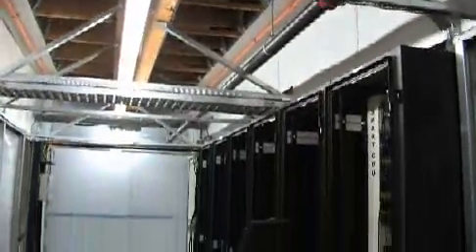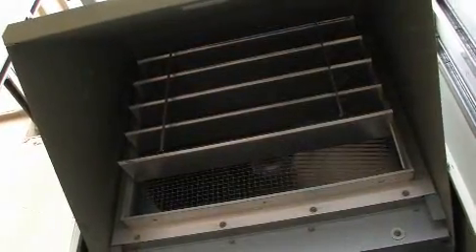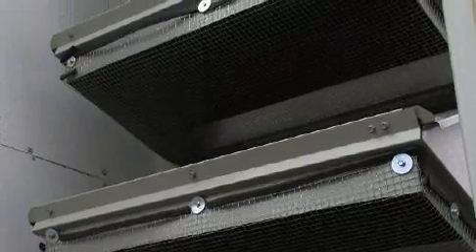So Intel decided to do the proof of concept at this site in a double-wide construction trailer, quite literally, with 4 50-ton air conditioning units because it was an inexpensive way to prove the theory.